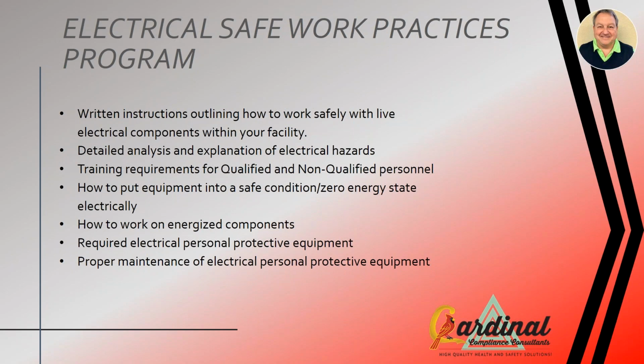We also then need to enforce putting things in a zero energy state or a safe state, and that's sometimes called being in an electrical lockout tagout condition. It's a little different than authorized lockout tagout because we're going to use their skills as electrical workers to prove and verify there's no voltage over 50 volts that can hurt anyone. There are a few extra steps required, and it is very important. This is something new they're pulling forward into the regulation of 70E. It used to be in the background, back in the annex, but it's important, and they pulled that forward.